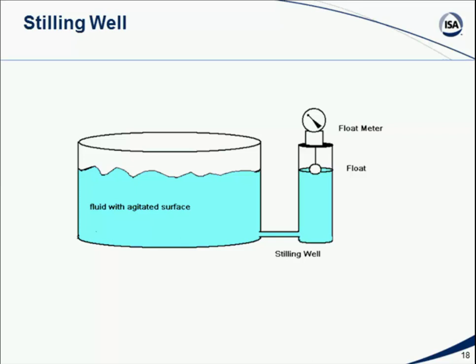We talked a minute or two ago about a sight glass, and I said the sight glass is where we tap off of the tank and come out to a vertical column. And that would allow us to take a look at the level, because the level in this outside column will be the same as in the tank itself. Well, we can make use of this principle. We can attach a stilling well to a tank, and we can put our float tape system on the stilling well. And the stilling well, because it is coming off, as you can see in this case, the bottom of the tank, we don't have the same problem with surface agitation.